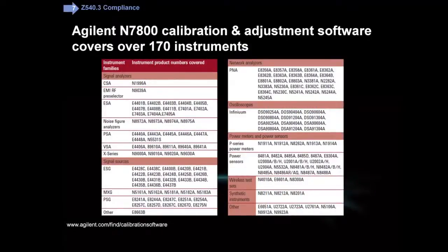If you have your own calibration lab and like to self-maintain, the N7800 calibration and adjustment software platform is something you may already be using or might want to consider. For over 170 instruments, we make our service software available under license. When you select the 17025 mode in the N7800 software, you are also meeting Z540.3 using Method 5.